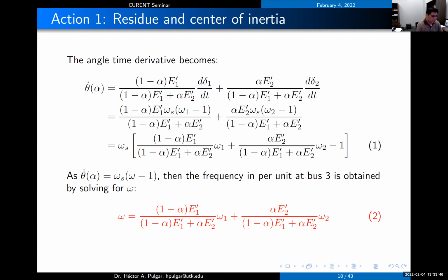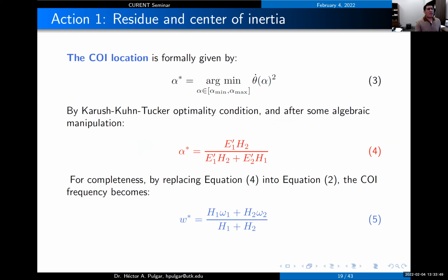Our initial idea was that optimal location should relate to the inertia in the system. But inertia is hard to describe, since one generator's inertia might be very different from the motor's. The equivalent inertia seen at bus 3 will be some combination of those, which is what we call the distribution of inertia.